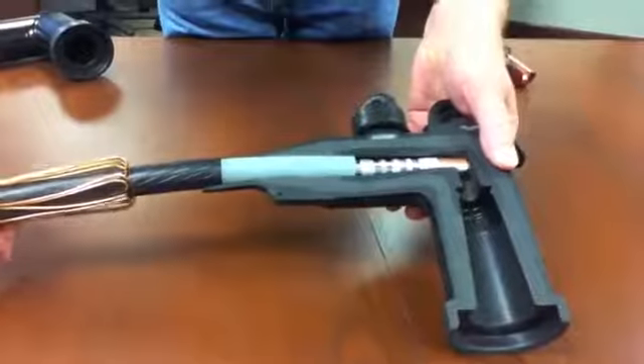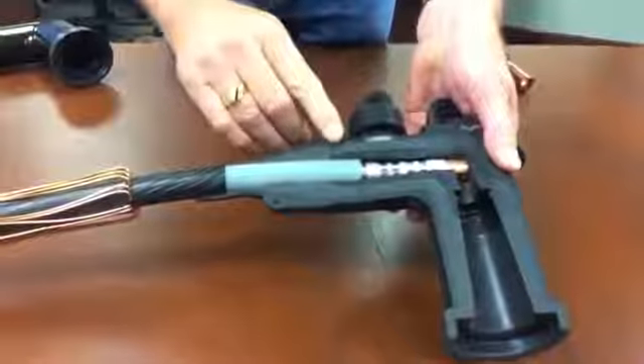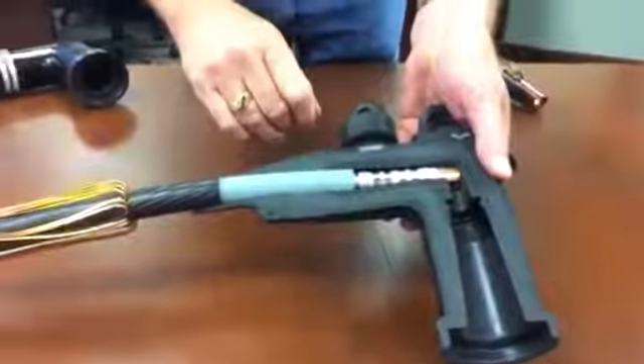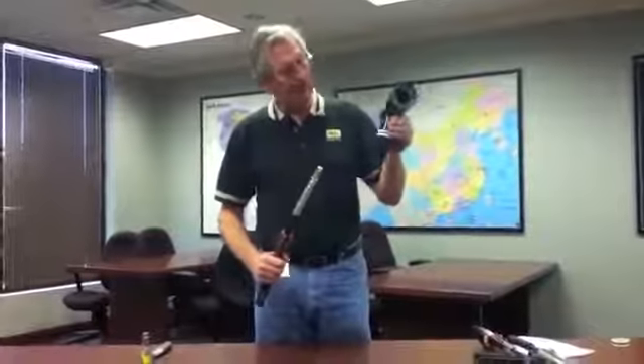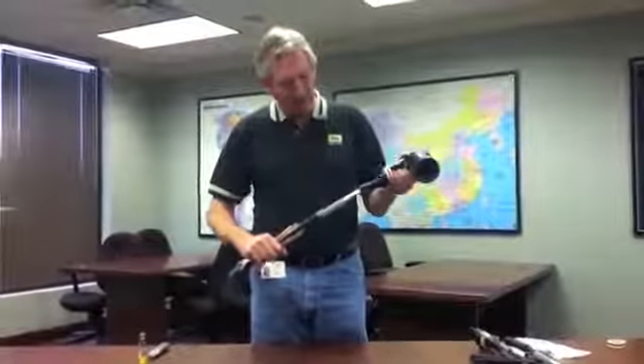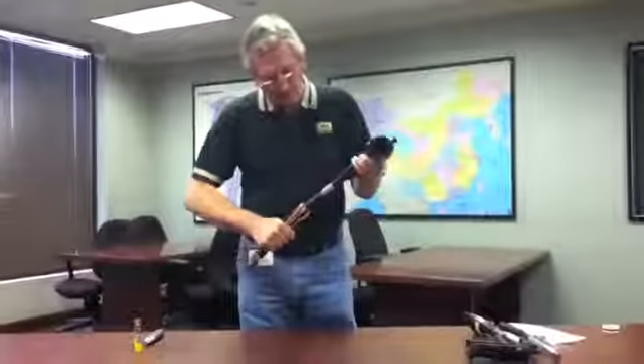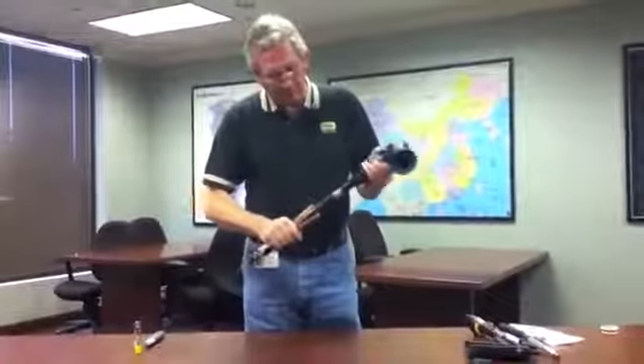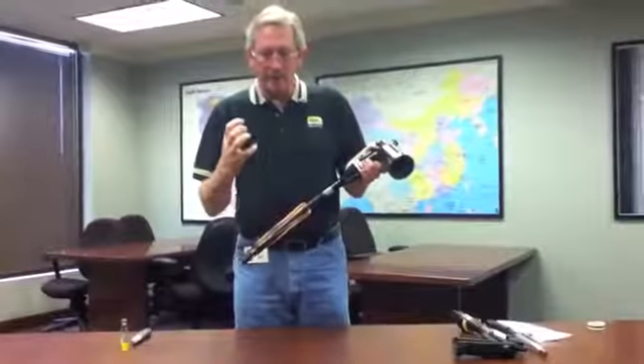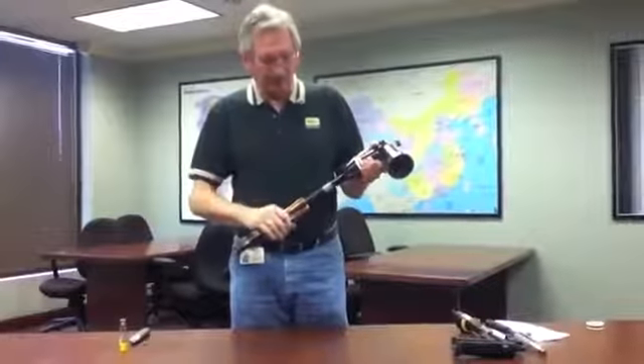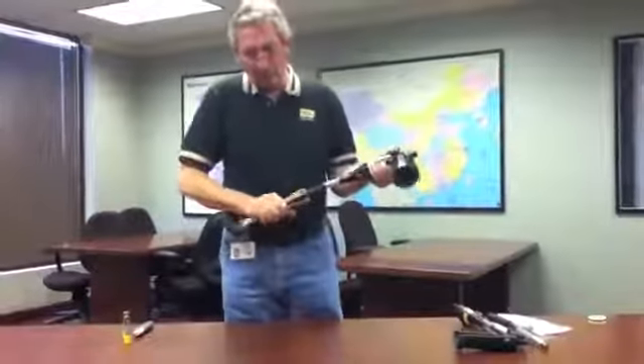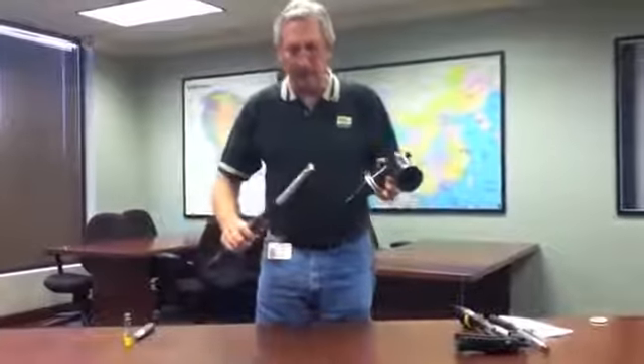Without proper lubrication, the assembly forces will be greatly increased. I have here a cable that, again, is properly prepared with the exception of a bevel on the end. And I've not lubricated the cable nor the housing. This housing is sized for this cable. As you try to assemble it, you're met with a great deal of resistance because the rubber is not sliding on any lubricant. I'm now going to lubricate the elbow and try it again.